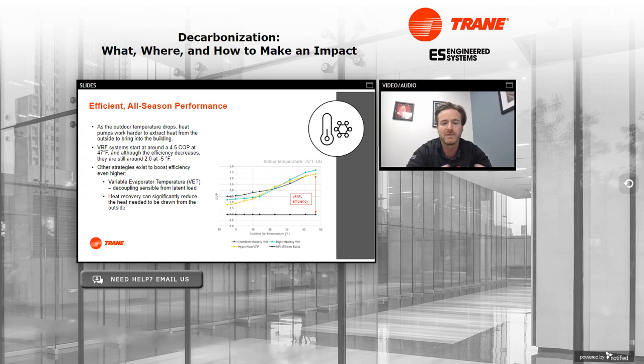So if you figure your coefficient of performance is how much heat are you getting per 1 unit of energy, with electric resistance heating, where you're just directly using electricity to heat the space, consider that to be a COP of 1.0. VRF is at a COP of 4.5 at milder conditions, let's call it 47 degrees, which is where AHRI rates VRF systems, and most VRF systems are rated at a 4.5 COP. So looking at this chart on the right that compares VRF to electric resistance heat or boiler, you're 450% more efficient at 47 degrees than you would be using a conventional system, just burning fossil fuels or using electric resistance heat.